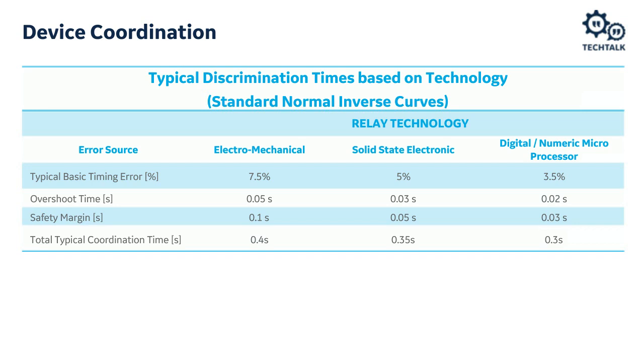You know, if we think of this as something like an EM relay, which is an induction disk relay, there's calibration that needs to take place, and over time that calibration can drift. That's why we have such a much larger basic timing error that we're accounting for, or budgeting for, in this CTI with the electromechanical relays versus the microprocessor-based relays. There's also the issue of overshoot.